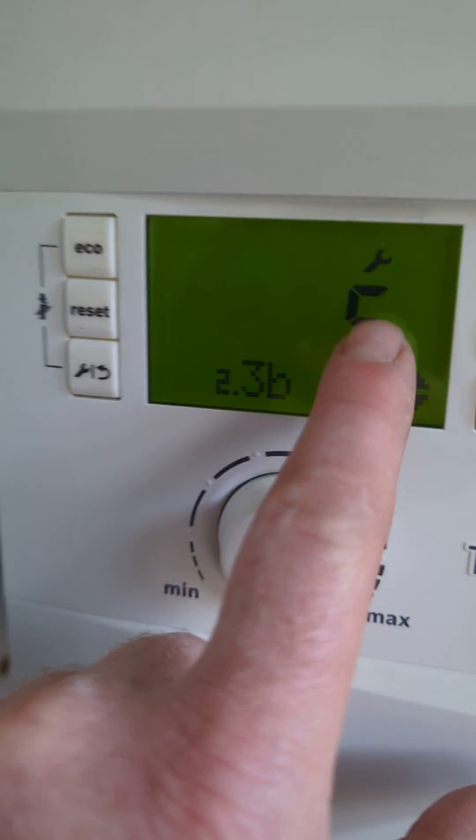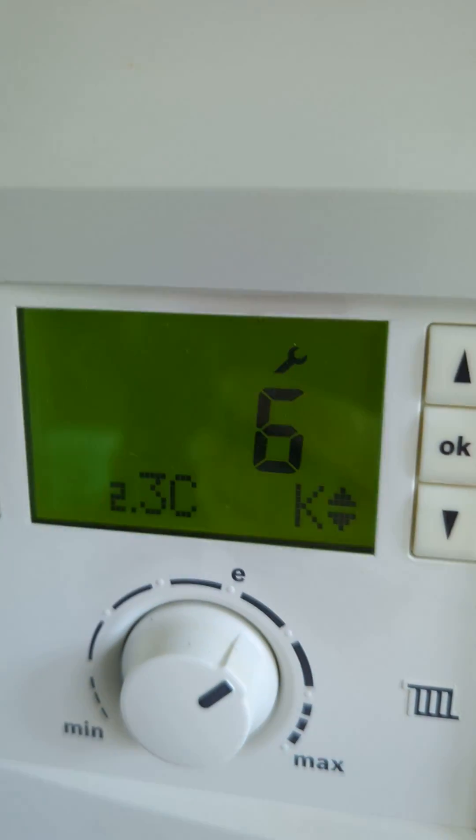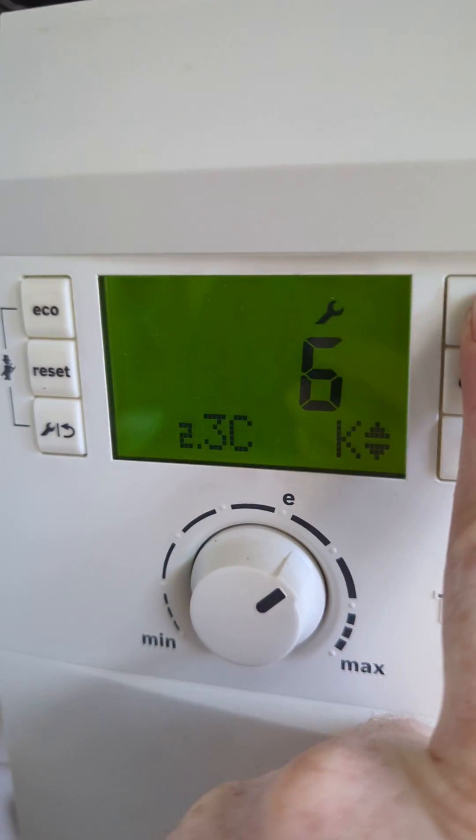This is the same anti-cycling but in degrees C — the boiler won't fire if the heat exchanger hasn't dropped by 6°C, but we can also change this should you want.